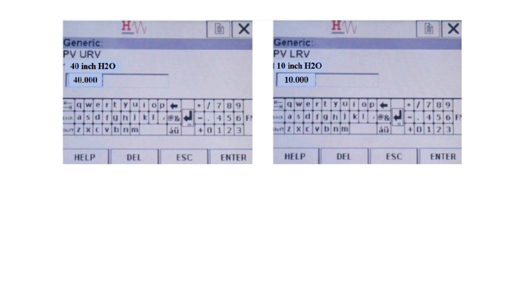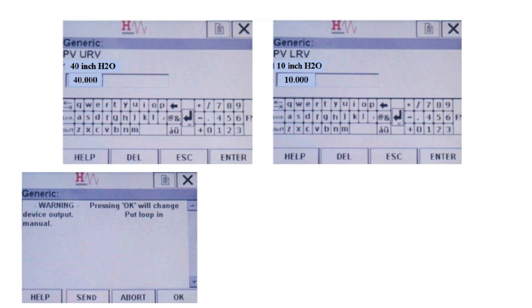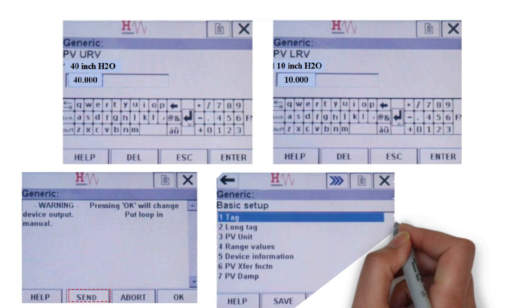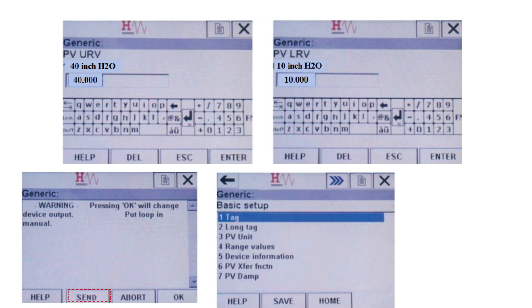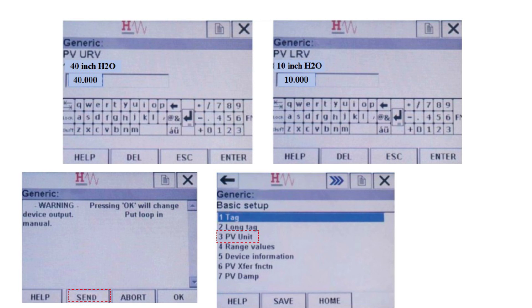As you can see, when the edit screen appears, you need to enter the upper range value and lower range value. After this, press the enter button to confirm these values. The change will not take effect until it is sent to the device, so tap the send button to send the range to the device. Now, to change the unit of measure, select the PV unit option from the basic setup menu, and select the unit which you want to set for the device, then press the enter button to confirm.